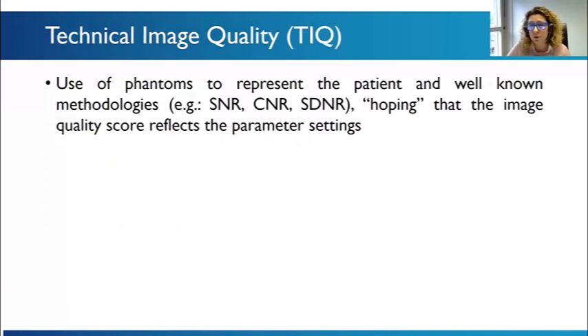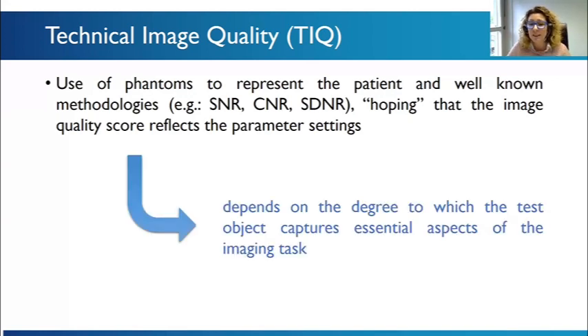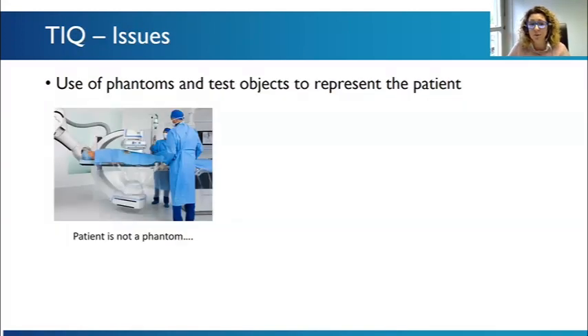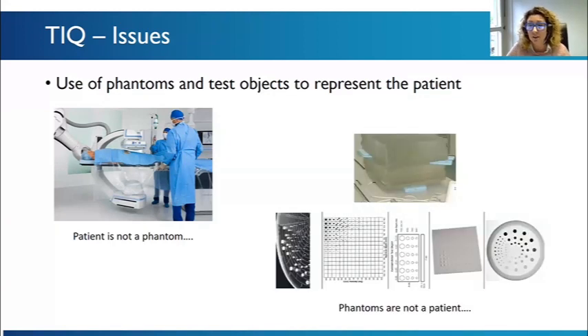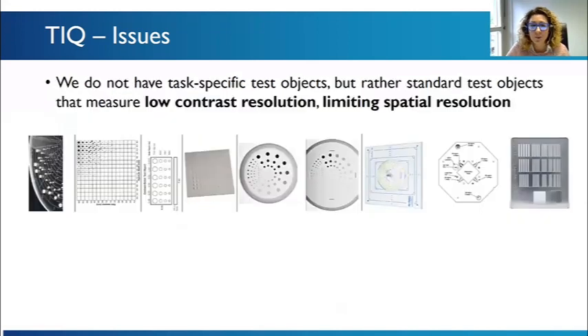So what we normally do is use phantoms to represent the patient, and also well-known methodologies like the signal-to-noise ratio, the contrast-to-noise ratio, and so on, hoping that the image quality score reflects somehow the parameter settings. Well, this depends on the degree to which the test objects capture essential aspects of the imaging task, and that's the challenge, actually. We use phantoms and test objects to represent the patient, but the patient is not a phantom, and phantoms are not really patients. We don't have specific test objects, but rather standard test objects that can measure low contrast resolution and limiting spatial resolution.